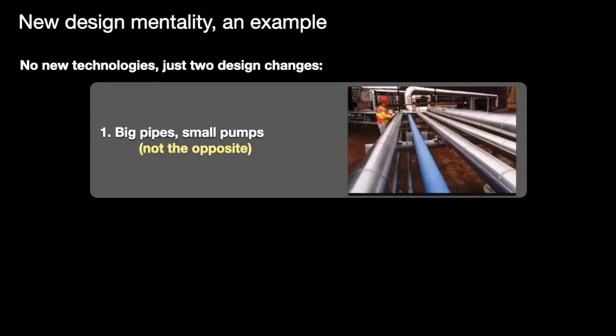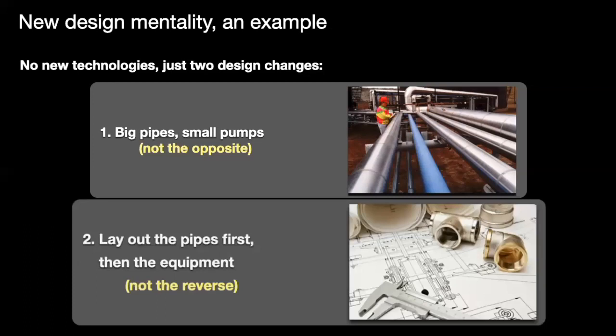So their size, and roughly their capital cost, will fall as nearly the fifth power of pipe diameter. Yet the capital cost of the fatter pipe rises as only about the second power of diameter. So when we optimize the pipe as a component, we pessimize the system. Instead, optimizing the entire system at once yields fat pipes and tiny pumping equipment, so the total capital cost goes down.